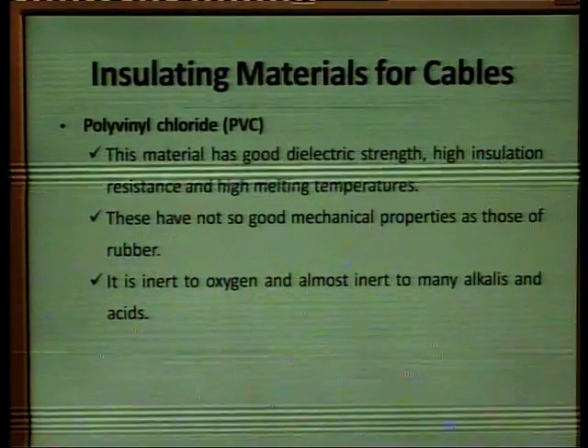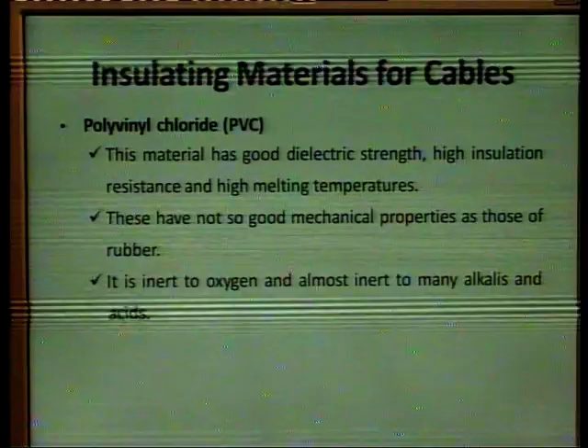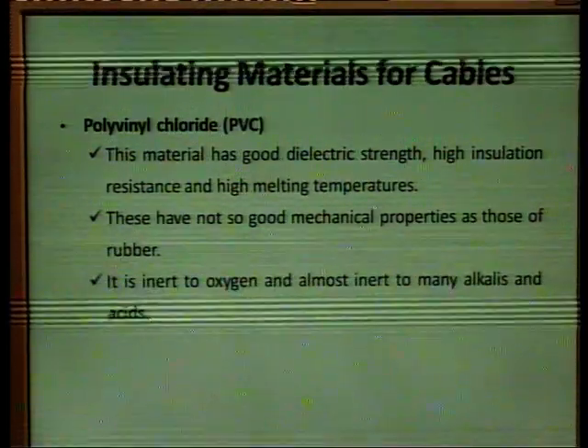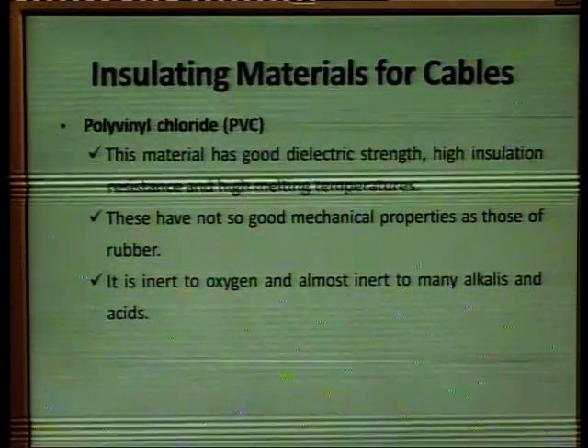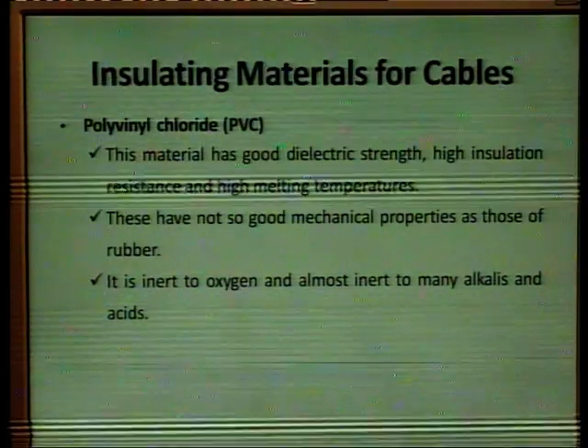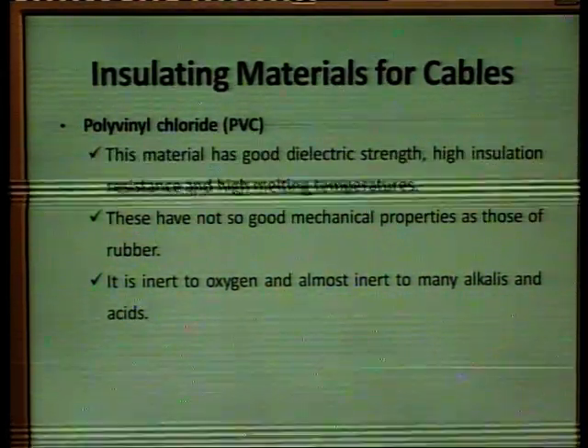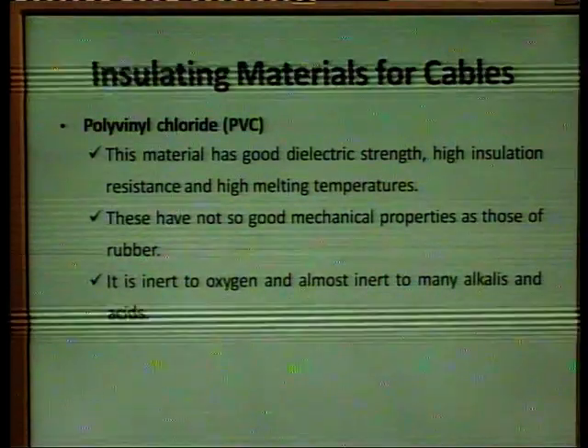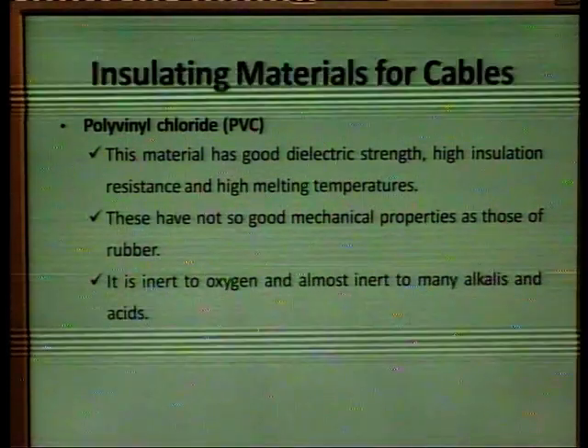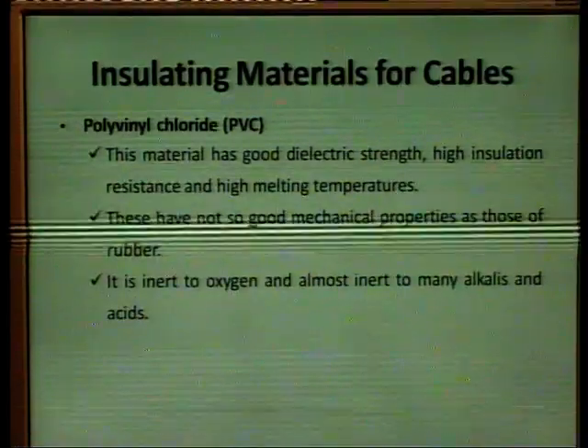Then the next material is PVC, the famous material known for insulation, that is polyvinyl chloride. This material has very good dielectric strength, high insulation resistance, and high melting temperatures. But PVC does not have such good mechanical properties as those of rubber, and it is inert to oxygen and almost inert to many alkalis and acids.